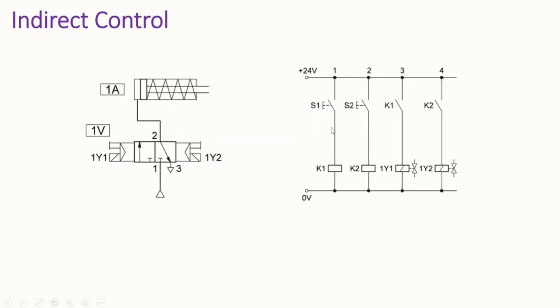Looking at the electric circuit, we have two switches connected to relays K1 and K2. These two relays are connected to two make switches K1 and K2, both in the open condition, and they are connected to two solenoids which are connected to control valve 1V. When talking about indirect control, we are dealing with the combination of switches, relays, make switches, and solenoids — instead of a direct connection between switches S1 and S2, we have the relays K1 and K2 making the connection between the switches and solenoids 1Y1 and 1Y2.